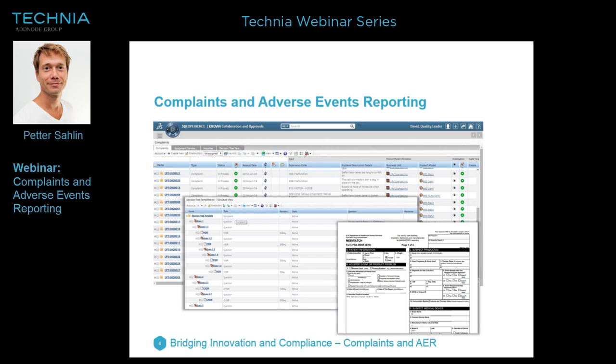In the end, the complaint should trigger the appropriate actions, which, if they are severe enough, would typically be a CAPA. The CAPA in itself would typically lead to a change, which might involve one or many control documents, which will involve training activities, which will involve an implementation of a change or a new updated procedure, and which most likely will also trigger an engineering change, which has to be taken care of properly.